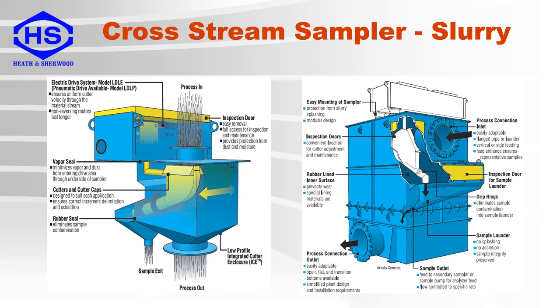These are two examples of cross-stream samplers used for slurry applications, mainly used as primary samplers. The one on the left is connected into a vertical pipe — the process slurry comes from the top and discharges out the bottom, and an electrically driven cutter moves across the process flow to remove an increment. The one on the right is for horizontal flows; the process is connected to the top and the sampler discharges at the bottom. Again, a cutter is driven across the process flow to remove an increment. In both examples, the increment discharges through an integrated launder.